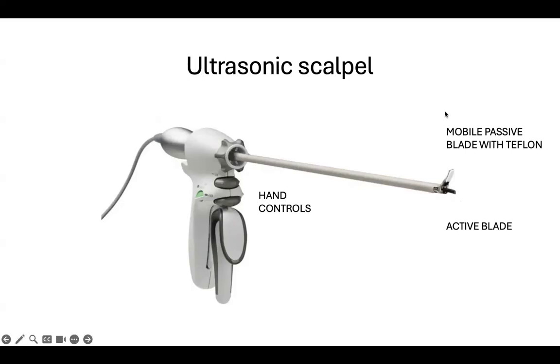So for example, if you want to coagulate a vessel, or be it any tissue, you have to hold the tissue against something so that the coagulation can happen. So in principle, consider a vessel. The vessel comes in between these two blades, and this acts as a support, and this blade goes in and out in a fashion that it is not visible. It is 55,000 hertz, mind you, 55,000 cycles per second.